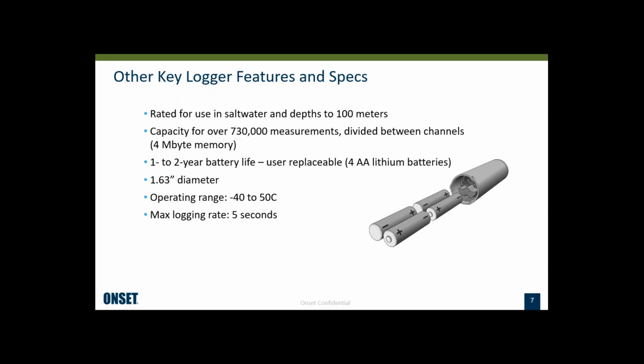The sensor, of course, is limited depending upon basically freezing. You don't want the sensors to get frozen. And the maximum logging rate on these is 5 seconds. I know our standard logging rate is 1 second, but just because of all the processing that's happening in these loggers, at this point, we're limiting the logging rate to no faster than 5 seconds.